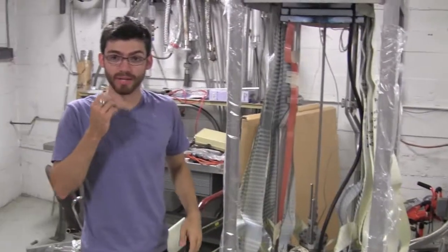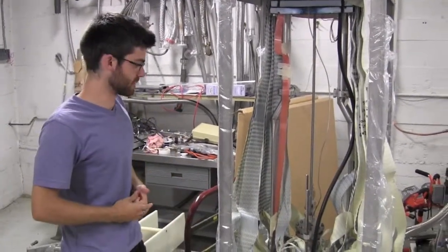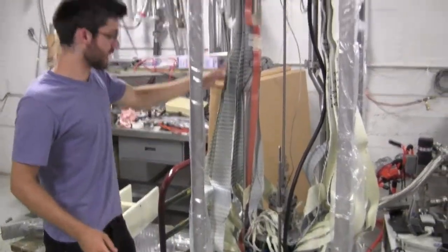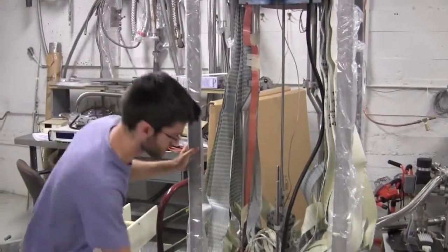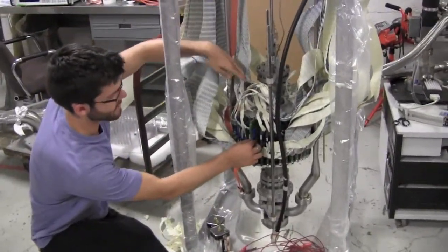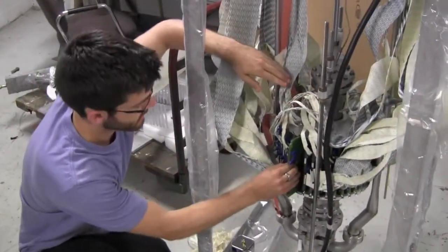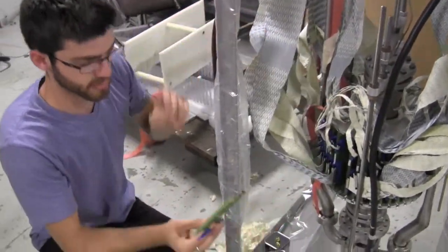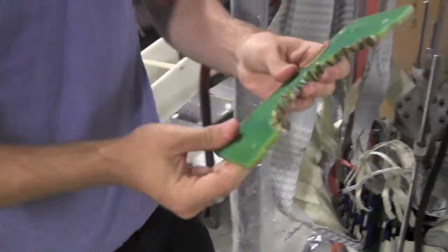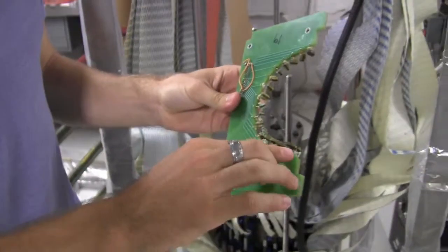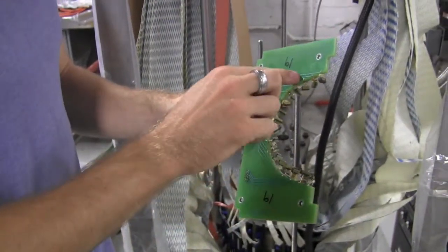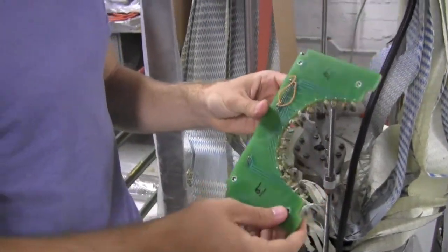Now, just briefly explain to you how this works because I know it gets confusing after a while. Basically, the wires come down and connect to these boards that are stationed all around the cavity that's inside of here. If we pull out one of the boards, I'll show you what we got here. We've got a board that perfectly fits around the cavity with resistors all around it. And the resistors, when they're in contact with the cavity and we have power running through it, register a voltage.